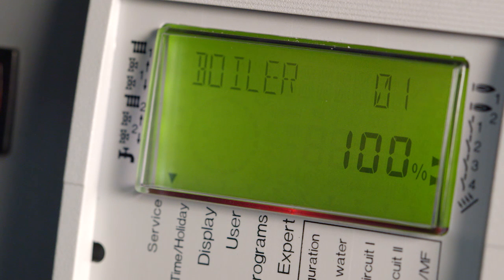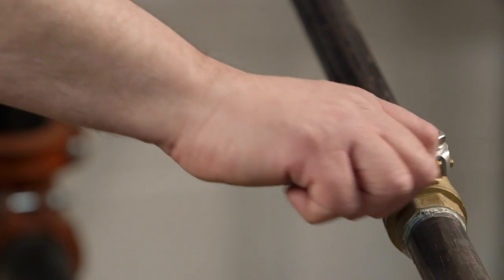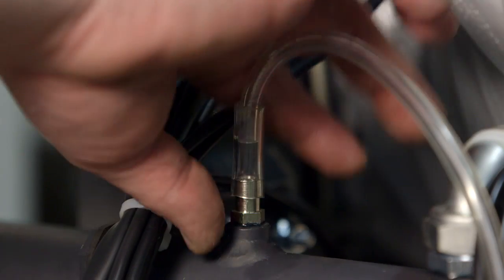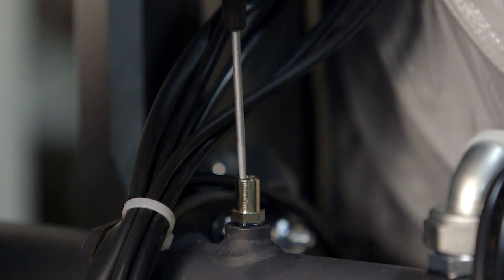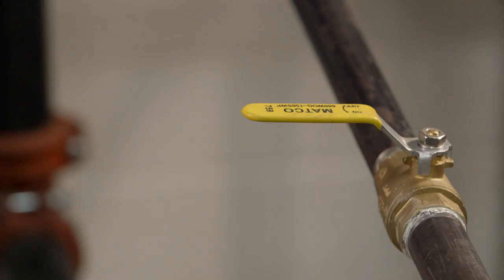Once your gas pressure is set, turn all modules to 0%. Shut off the gas valve. Remove the manometer hose and tighten the screw. And finally, open the gas valve.